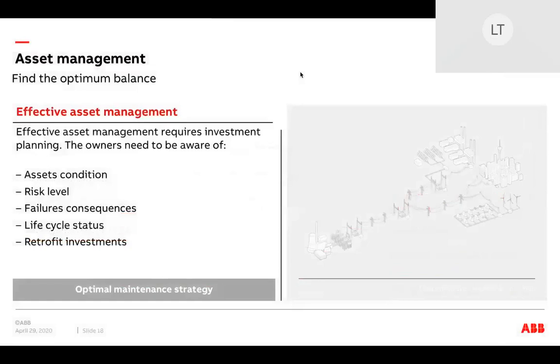For effective asset management, asset owners need to be aware of several factors: condition of the switchgear and breakers, risk of what happens if I lose a particular breaker feeder. Do I lose production or do I lose just the lights? Probability of failure in real time across all assets. What life cycle am I in with my switchgear? Are spares totally available? Is my equipment current or obsolete? And lastly but not least, when do I trigger service retrofits to extend the life of my switchgear and reduce impact to production?